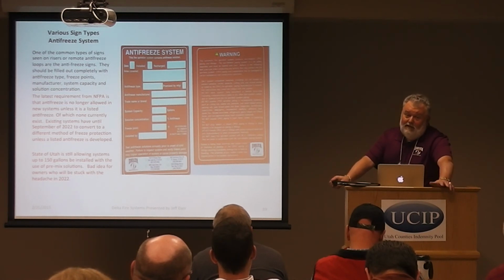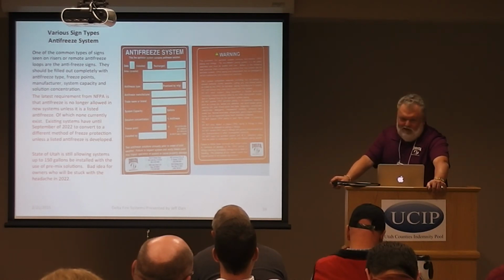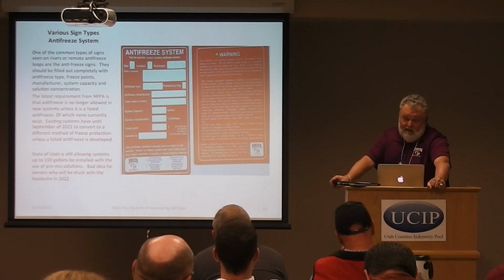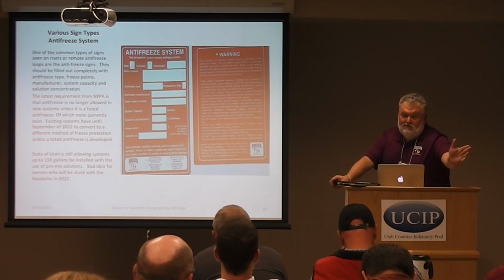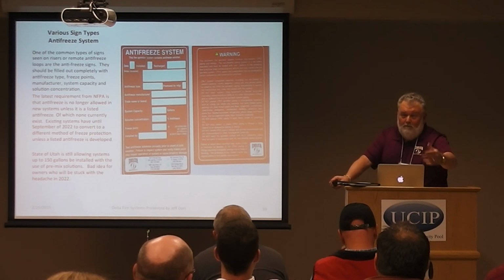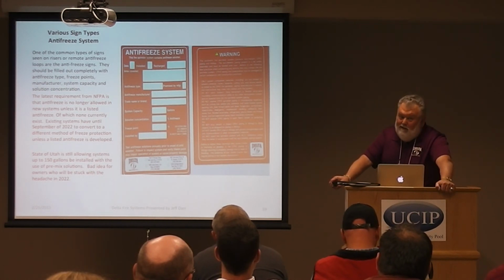And as a matter of fact, they're saying that by September of 2022, all existing systems will have to be replaced with either a listed antifreeze, which, like I say, none is out there, or they're going to have to go with alternative ways of doing it, either insulation, heat tape, dry systems. Systems already installed, they're not going to be able to do that. But the state of Utah has taken, from what I say, kind of like the ostrich with its head in the sand approach. They're still allowing new systems of up to 150 gallons of antifreeze using premix. The problem with that is we're seeing contractors out there stack 10 150-gallon systems off of one manifold for one building. So I think we're doing the end user, the owners, a big disservice.